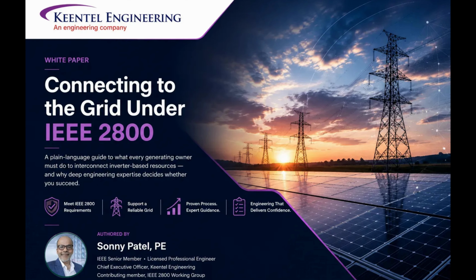IEEE 2800 is a performance standard, not a checklist. It tells you how the finished plant must behave, then requires you to prove it, on paper and in the field, across reactive power, frequency response, ride-through, power quality, protection, and modeling.